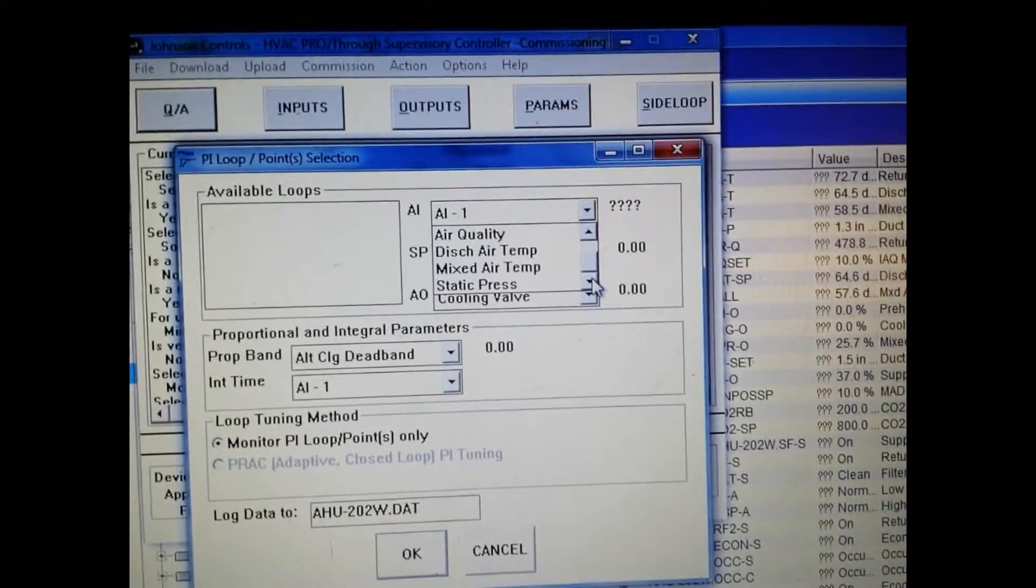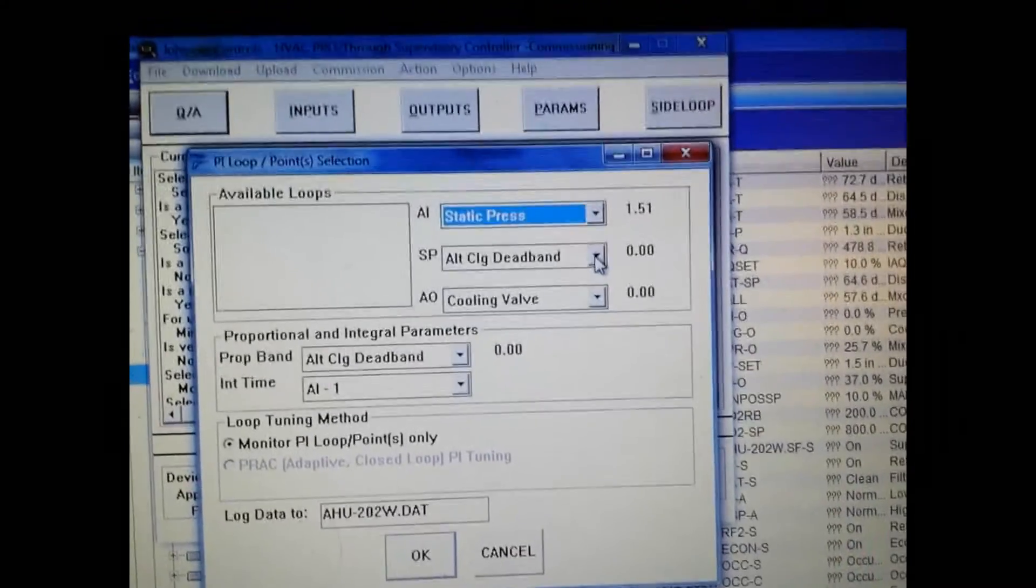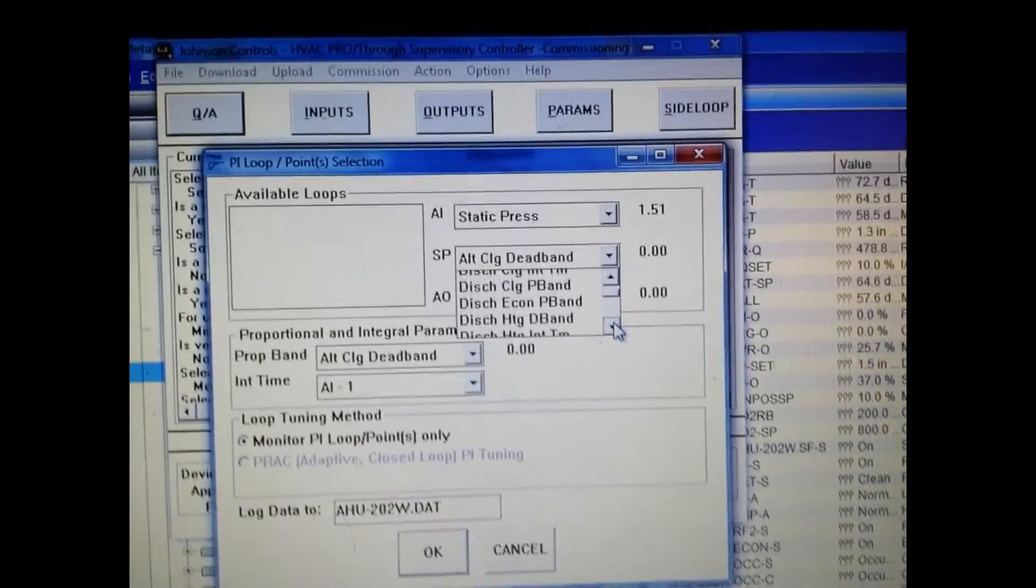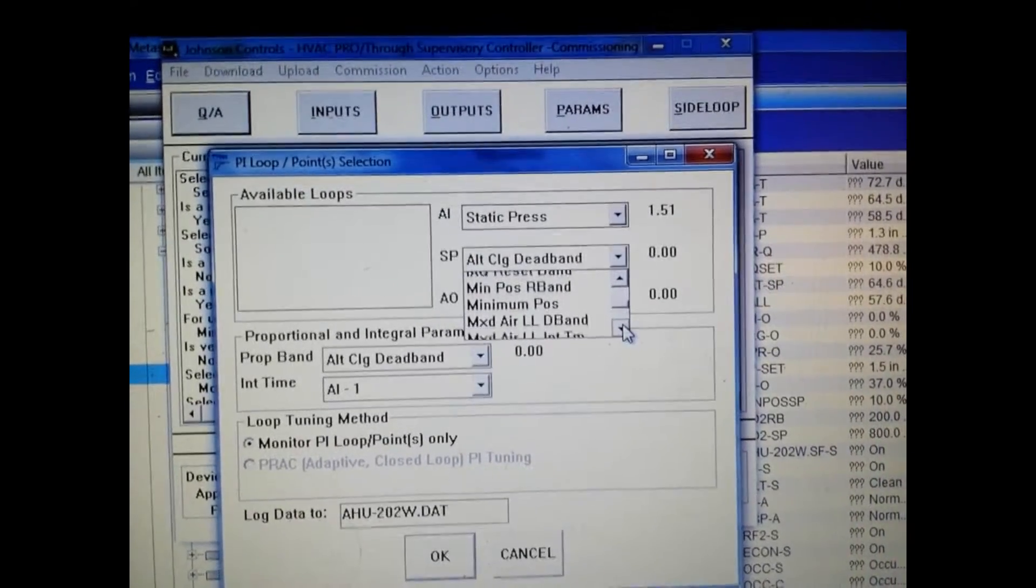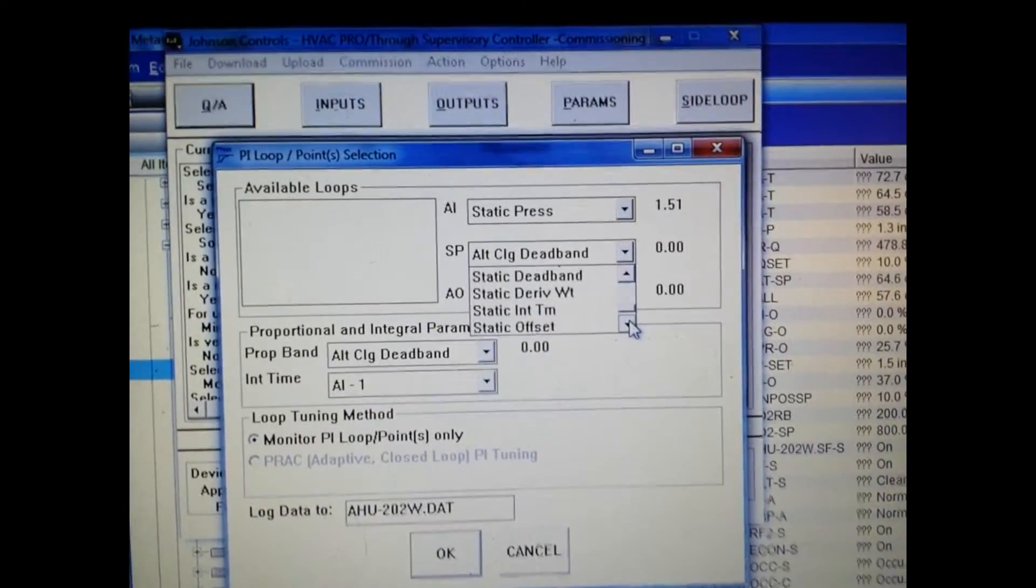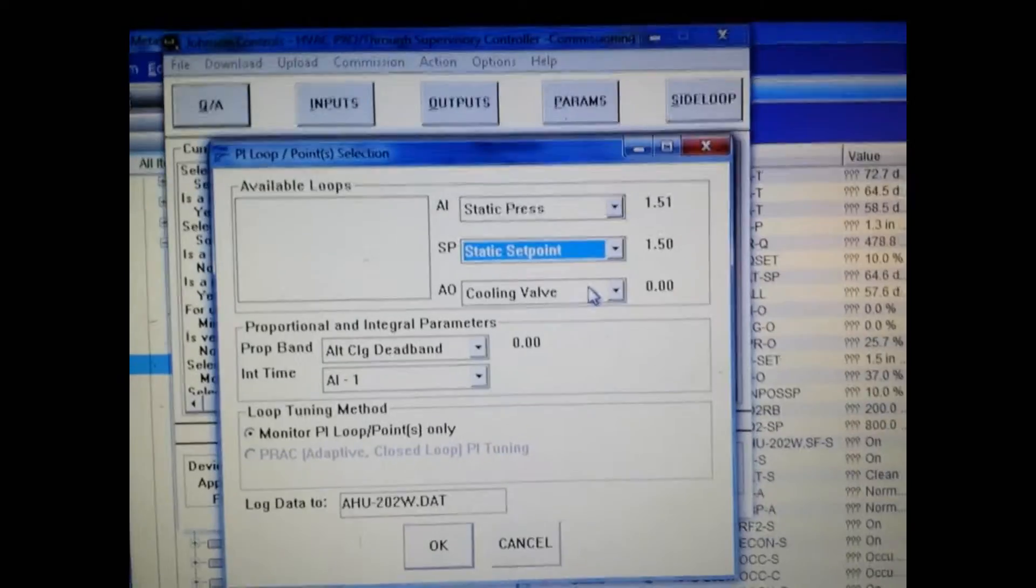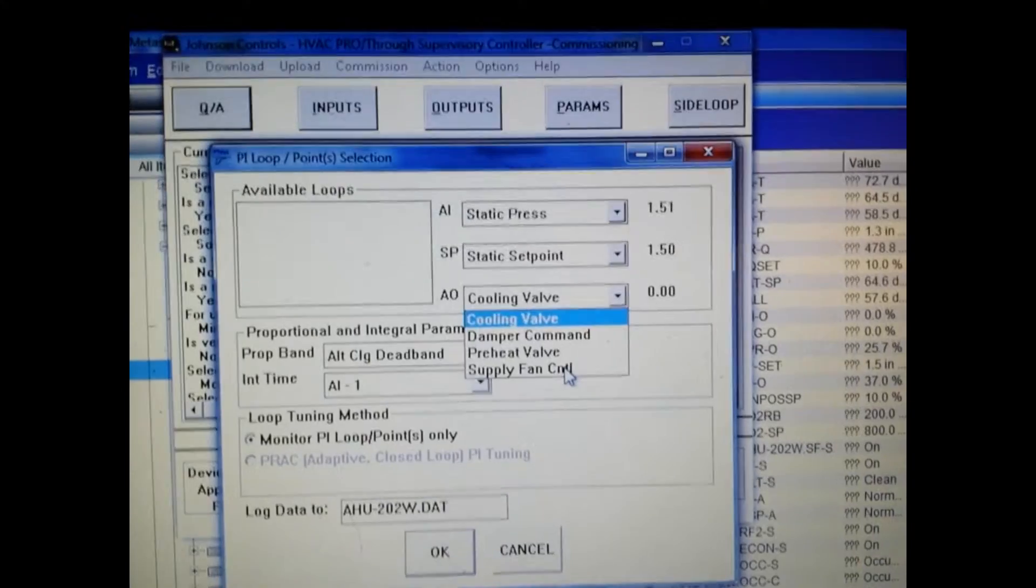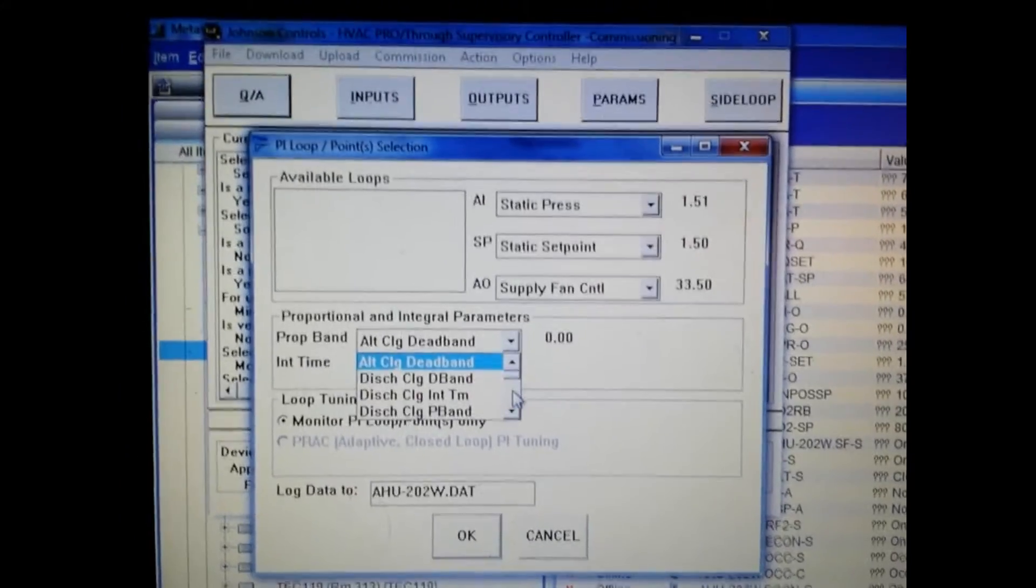Since we are going to be tuning the PID loop for the static pressure, what we need to select is of course the static pressure input. The set point value in this drop down tab is of course the set point for the static pressure that we're trying to maintain. If you are using a calculated pressure for your set point, I recommend that you put an override on it to lock it at a constant value. Our analog output is of course the supply fan command.